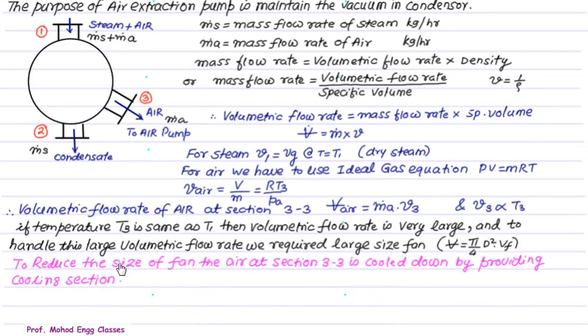And to handle this large volumetric flow rate, we require large size of fan, because volumetric flow rate is defined as the cross sectional area of pi by 4 D square multiplied by flow velocity. To reduce the size of the fan, the air at section 3-3 is cooled down by providing the cooling section.